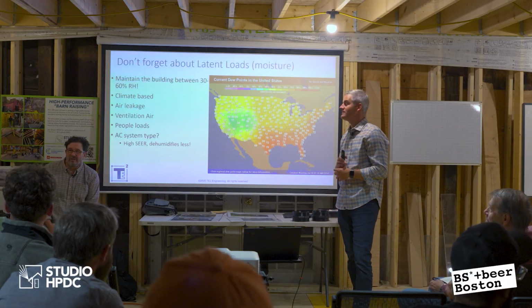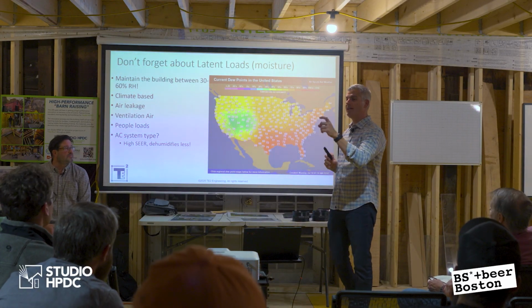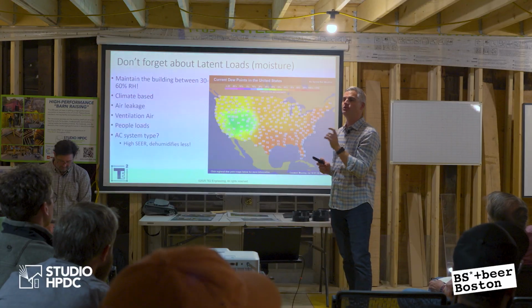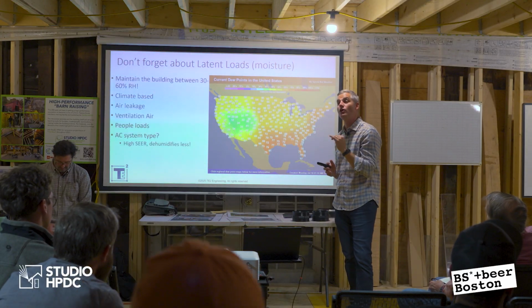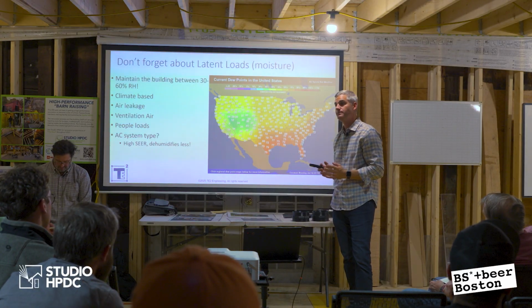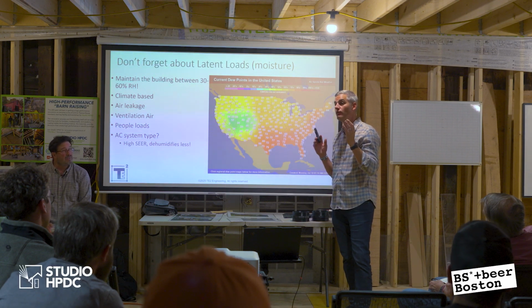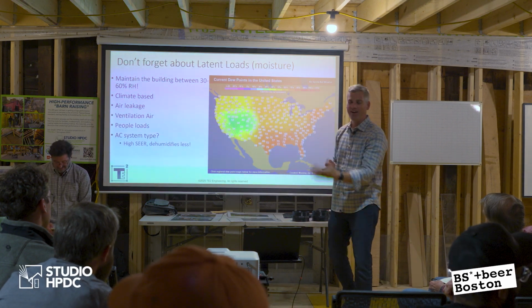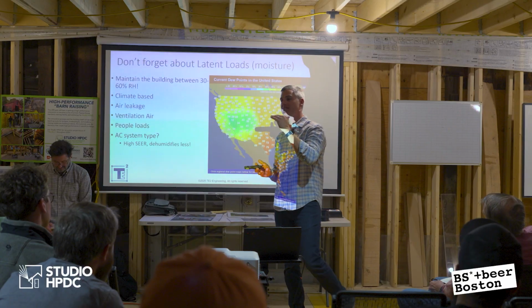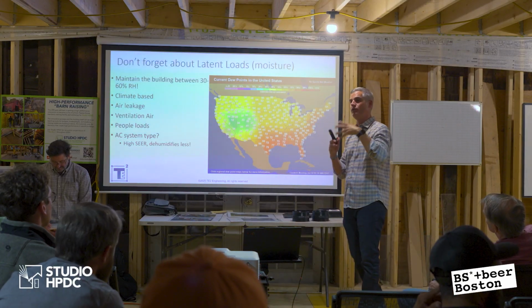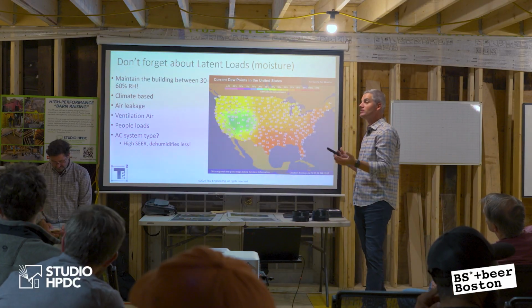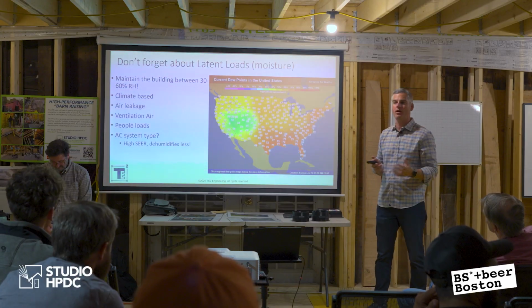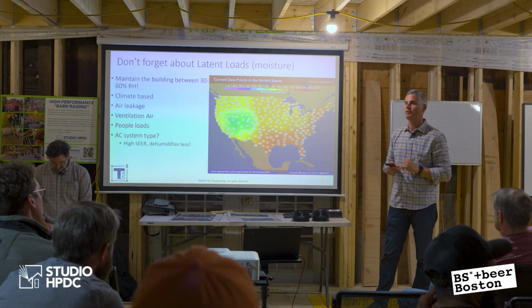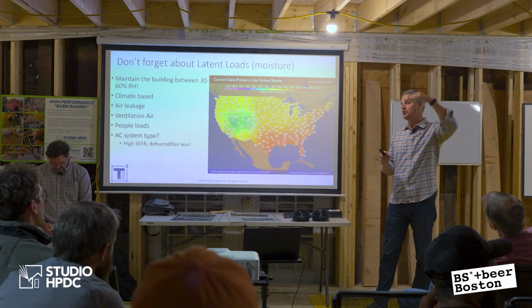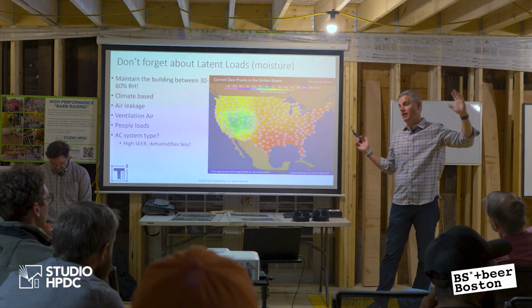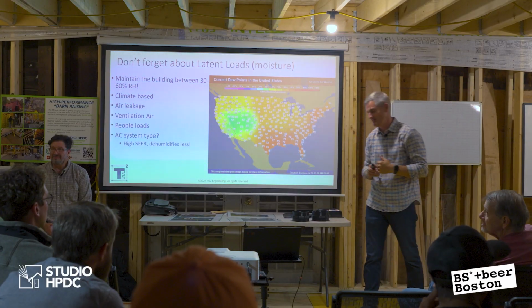And Sanco can give you the high temperature, but it can't cool. Right now the EPA regulation is that you can have R290 in a system if you have less than 150 grams of it. I know, it's crazy, but that's the EPA limitation right now. If you can get below that, we can make it work. Most of the 5-ton versions are going to be double or triple that in terms of refrigerant capacity. So we just need the EPA to shift that guideline up a little bit, and we're there.